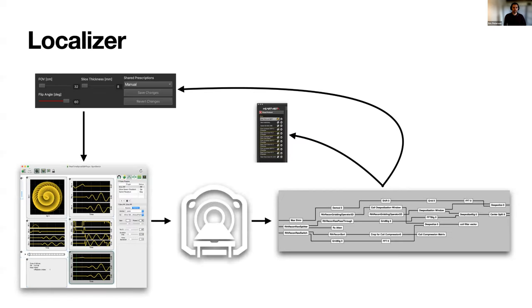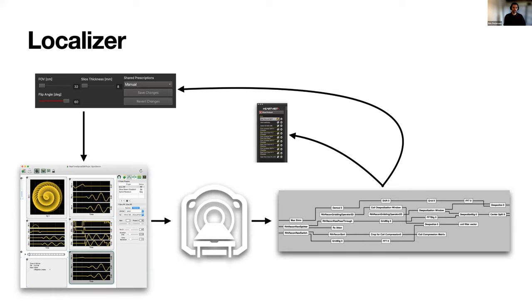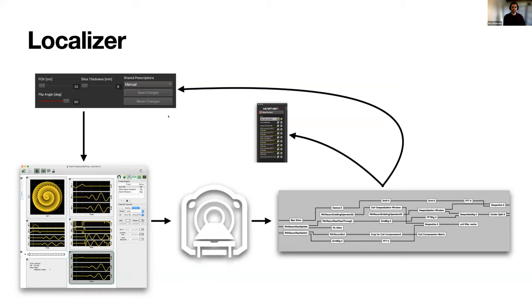What that looks like is you have your UI, make some changes, scan. The sequencer, which you don't actually see this view while you're running, but this represents the sequencer. Can make changes to your waveforms as you need—change the flip angle, field of view, geometry, whatever. Scan data comes back reconstructed and is then sent back. Whatever you want is sent back to the UI. Maybe you need to make some changes automatically there and also you can send to the other sequences in your protocol as you choose.